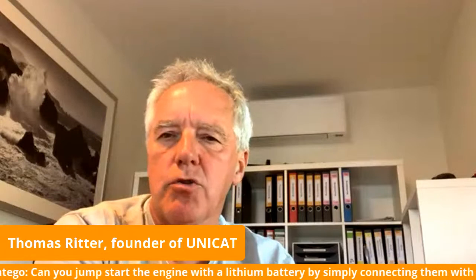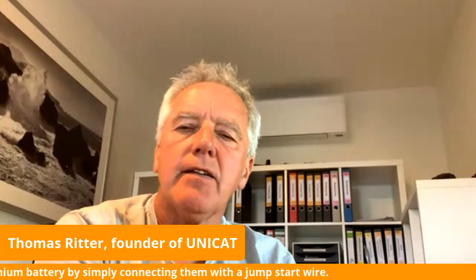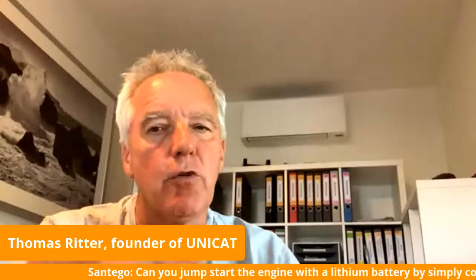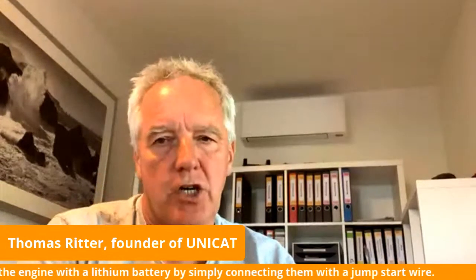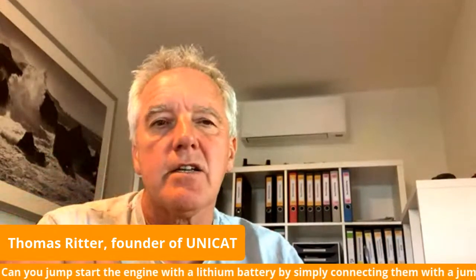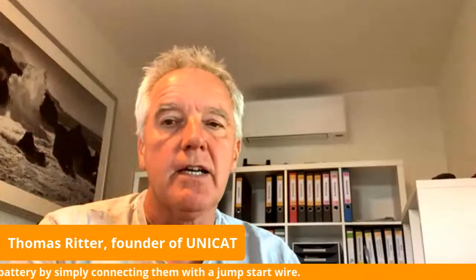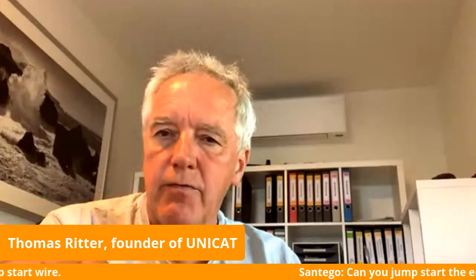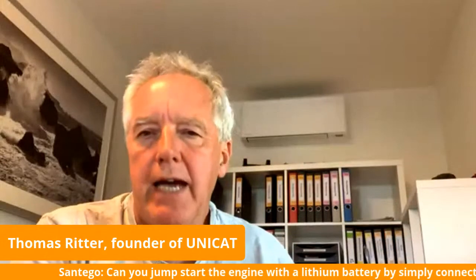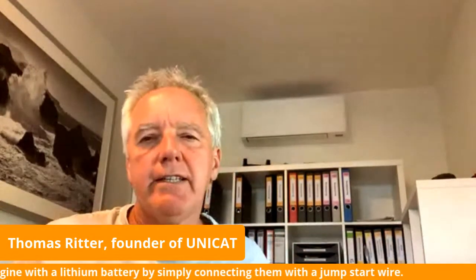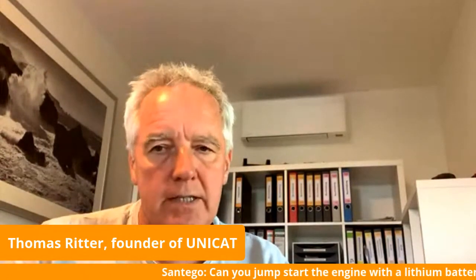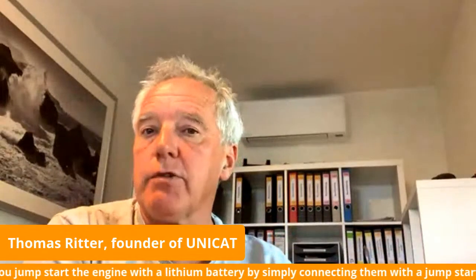You should make sure the voltage of the lithium batteries is not at the absolute peak, which only happens if the batteries are full and still being charged—then it can be above 29 volts. We know the regulators for 24 volt systems are set to 28 volts, so as long as you stay below 28 volts, your systems in the truck will handle that. But if your lithium batteries are not being charged, the voltage will not be above 28 volts, and you can connect both battery sets.